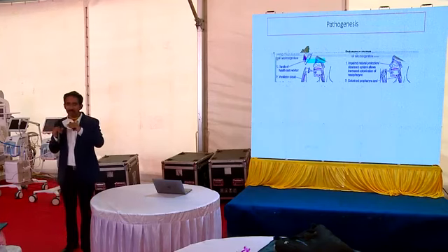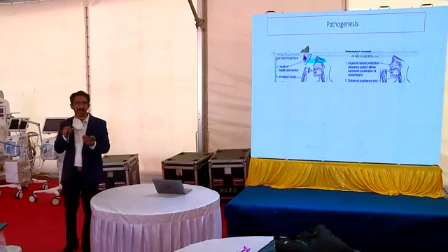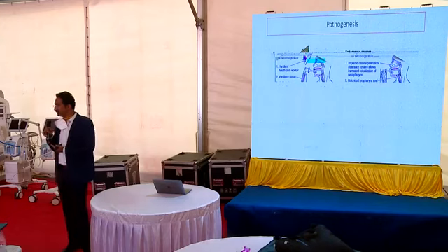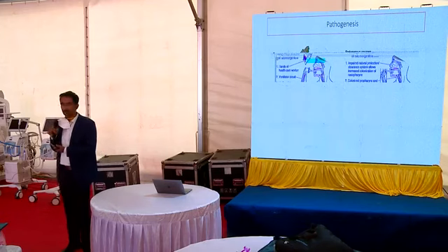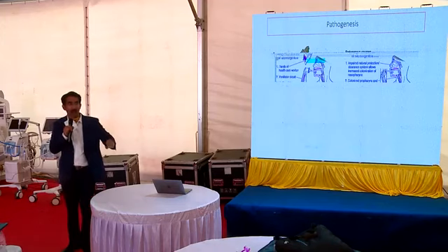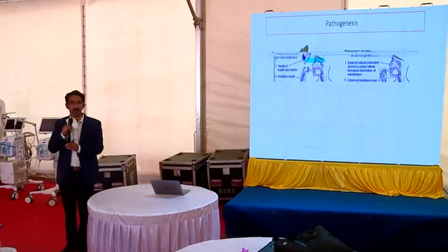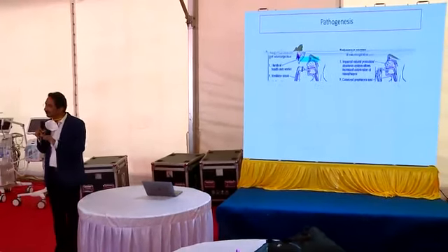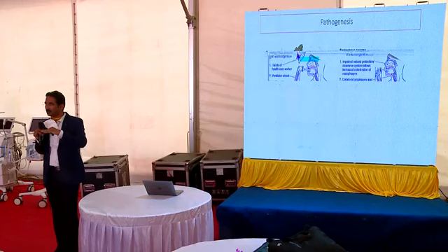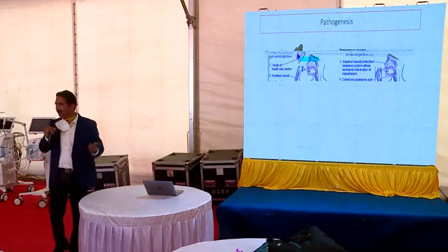The most common places of entry are through the ventilator circuits. It's a common practice that many people just sterilize and reuse ventilator circuits. If they're not stored properly, or if the sterilization of the equipment is not done properly, it can cause that. Humidification is another very important source. We have to make sure that sterile water is put in the humidifier and not non-sterile water. And the process of putting water into the humidifier is also important. You would have seen nurses puncturing the bottle many times, which often keeps leaking. The preferred route is to have a closed system. Most of these humidifiers have an automatic system where it fills when the water level comes down, and then it closes on its own.